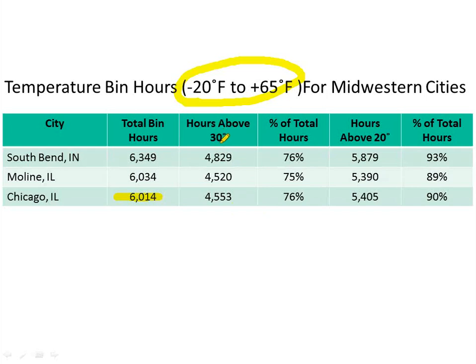If we look at hours above 30, so between 30 and 65, it's 4,500. It's more than half of the hours of the year. Or if you want to think of it this way, 76% of our heating time is between 30 and 65 degrees outside. If you look between 20 and 65, it's 90% of our hours. So 90% of our wintertime heating hours are between 20 degrees outside and 65.